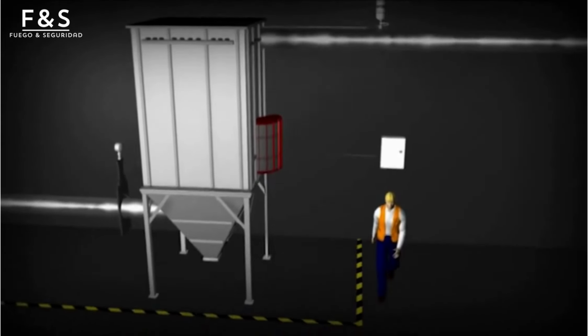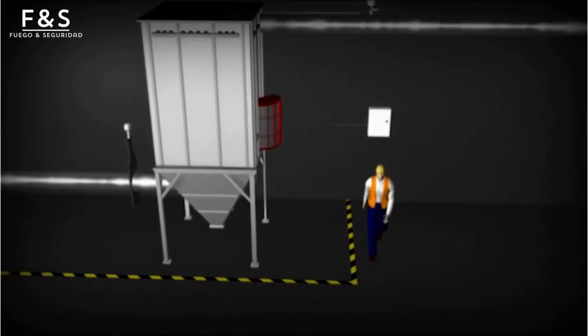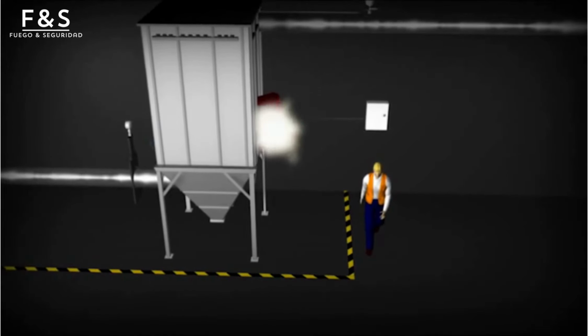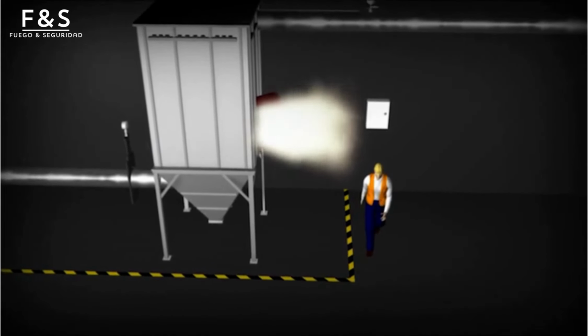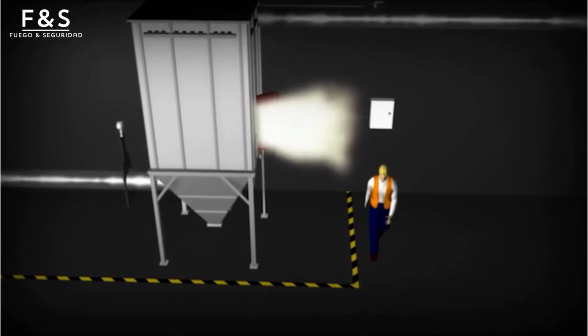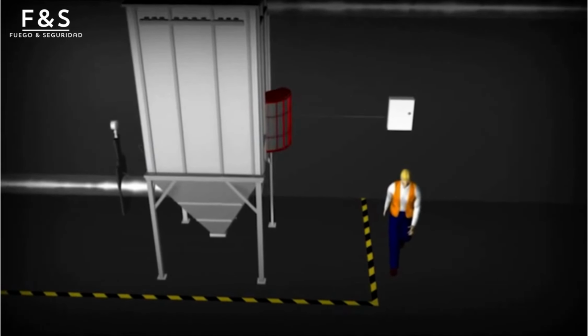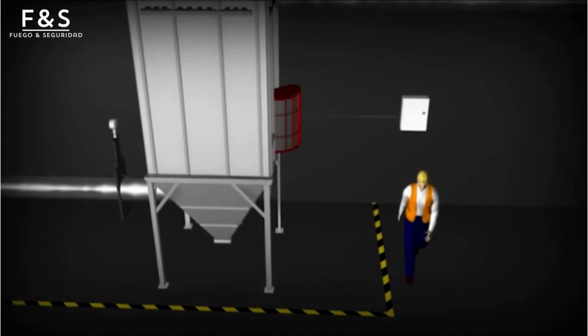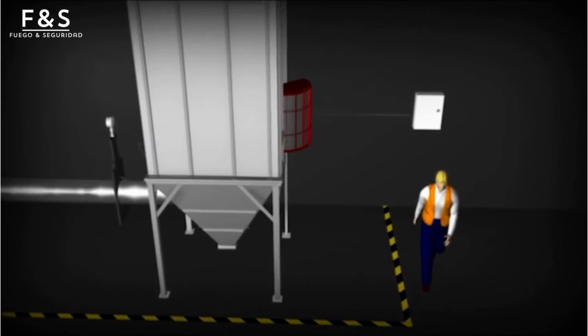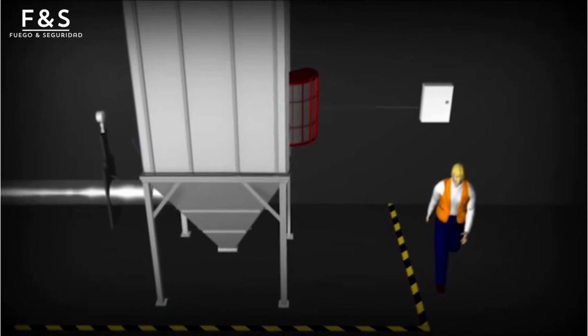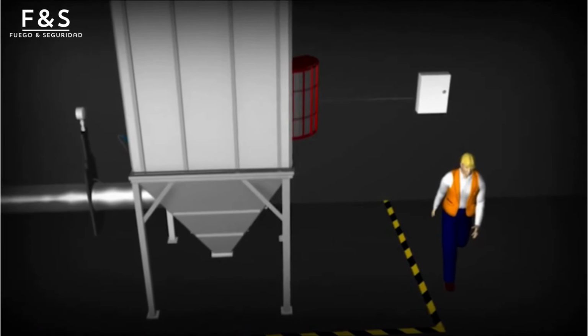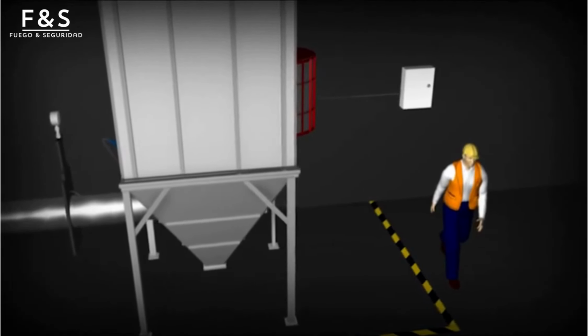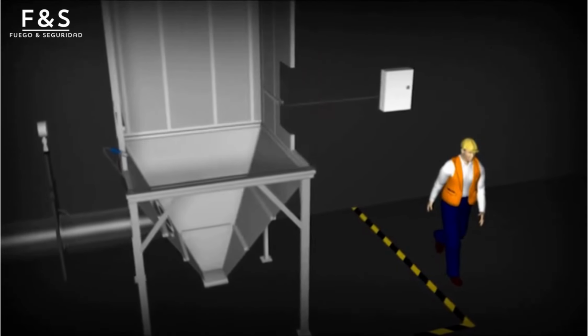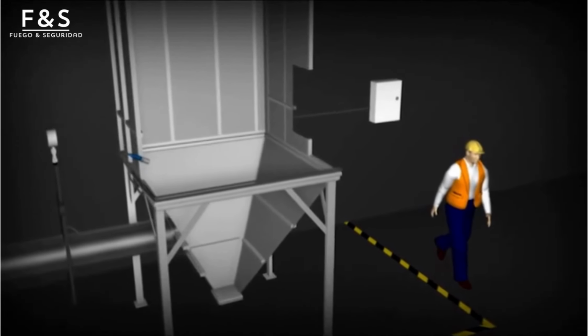Alternatively, when the process cannot be vented safely outside, the explosion vent opens and directs the fireball into a flameless venting device. The flames are extinguished as they pass through the flame arresting screens, allowing pressure release but preventing dangerous flames from entering the work area, protecting personnel, and preventing secondary explosions. It is also necessary to isolate the deflagration, preventing the transmission of the flame into interconnected vessels.